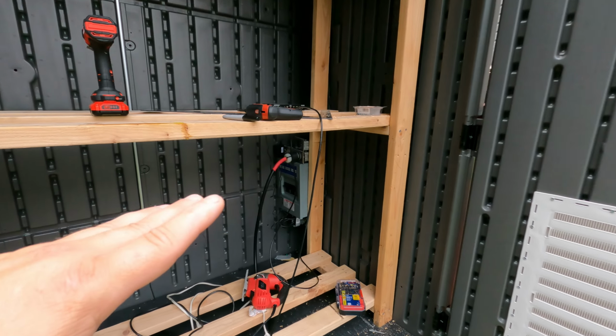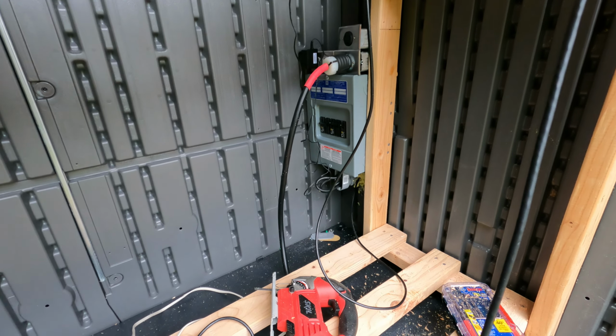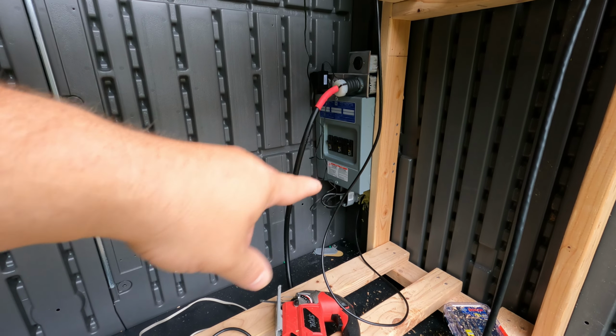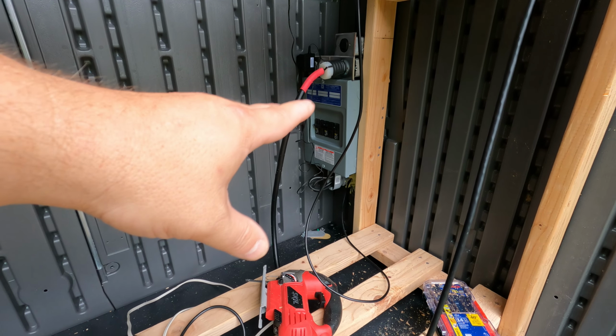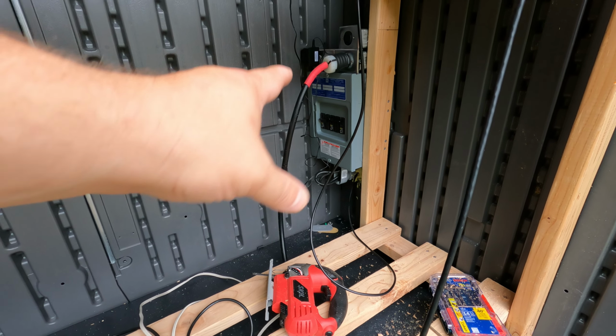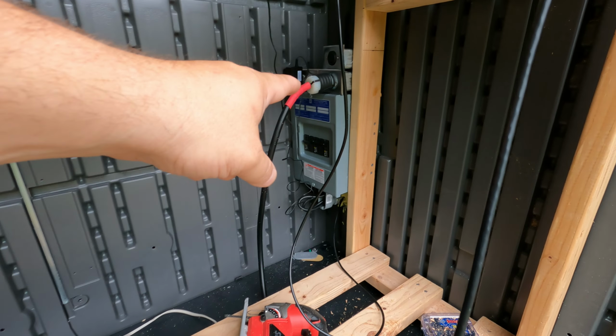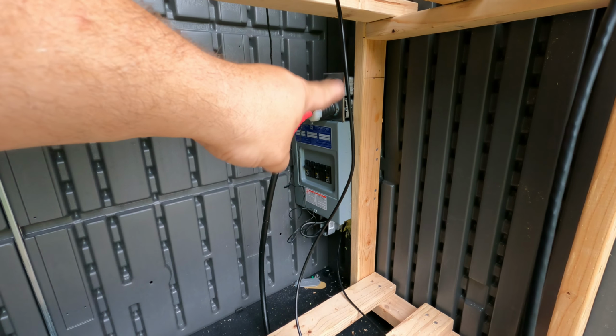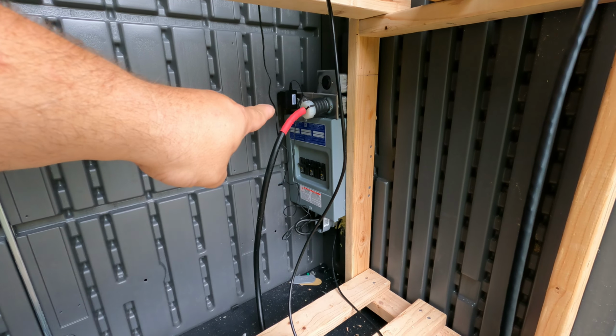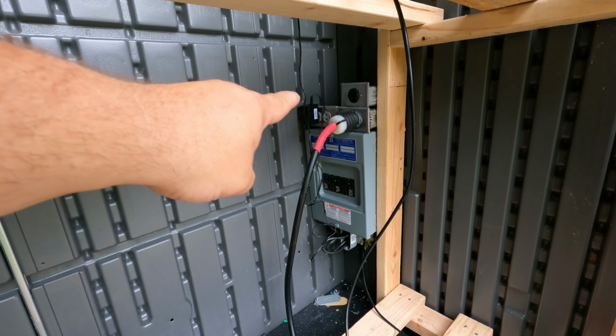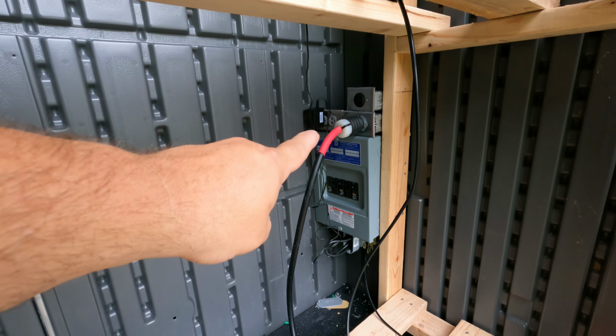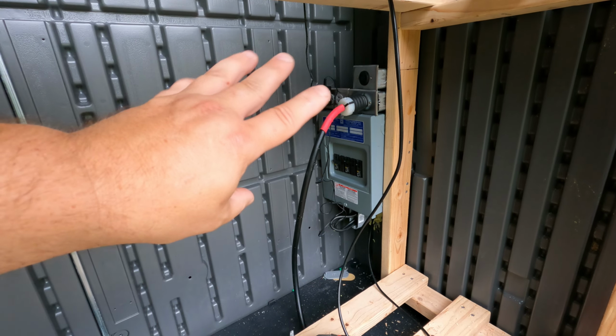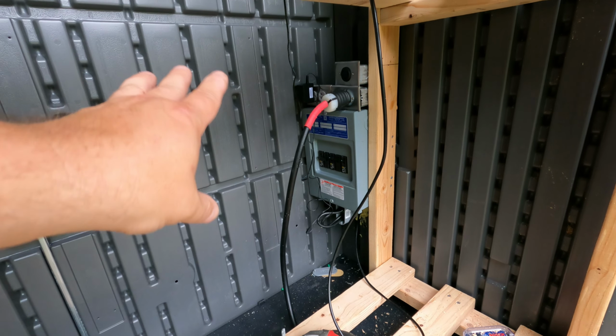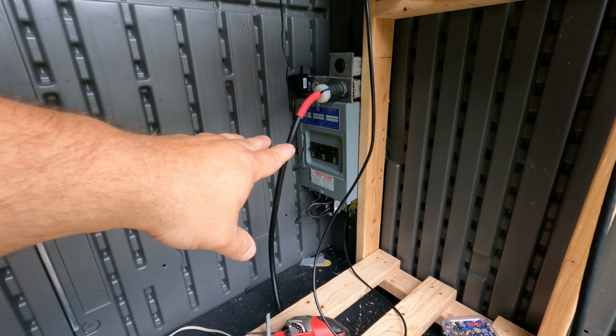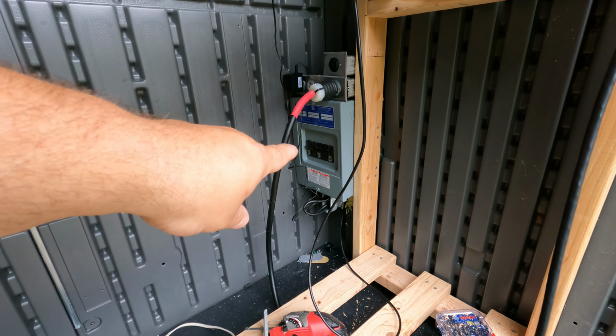With that being said, basically I ran a 60 amp breaker inside out to here with 2 gauge aluminum wire. So the wire is oversized for what I need to do, and the breaker is undersized. I have 2 30 amp 240 circuits, and then a single 120, 20 amp circuit back there for running the exhaust fan and other little 110 loads once we get to that point. Just a little 6 circuit breaker using 5 of the 6 circuits, mounted off to the side here.